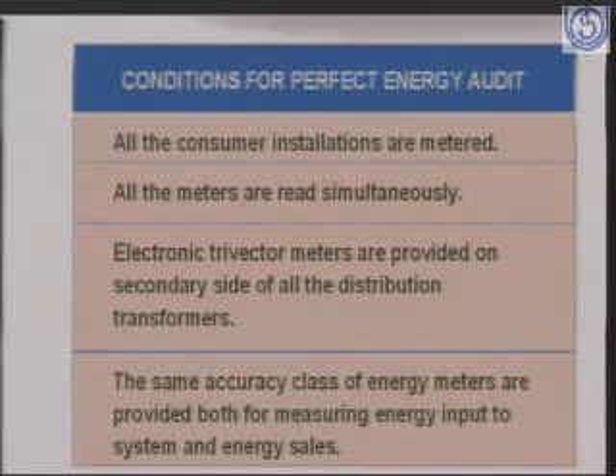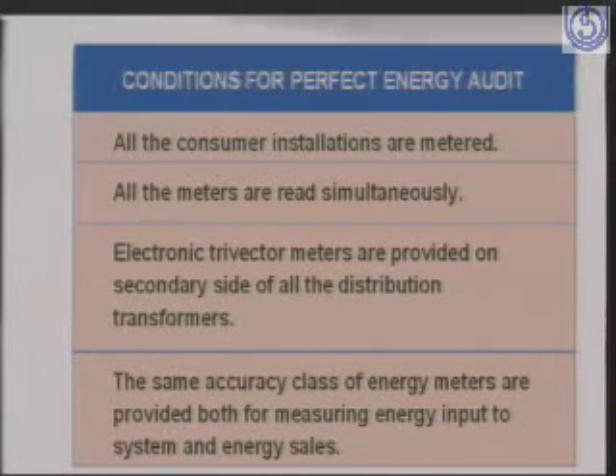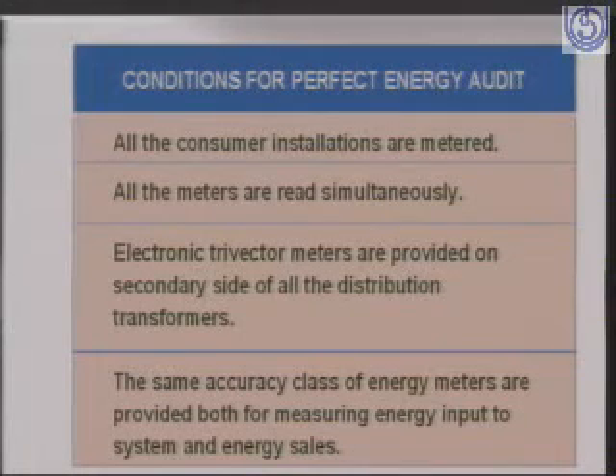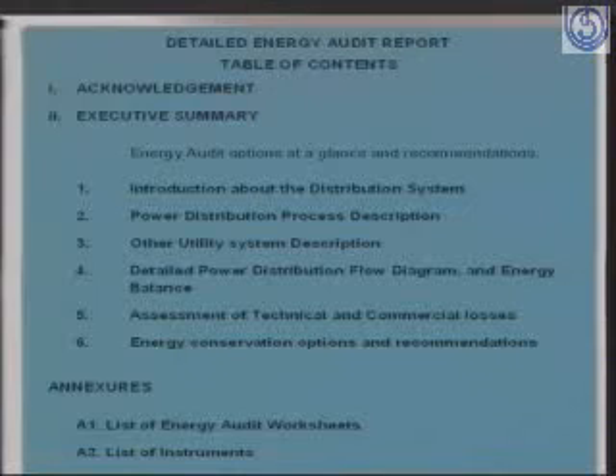So conditions for perfect energy audit: all the consumer installations are metered, all the meters are read simultaneously, electronic trivector meters are provided on secondary side of all the distribution transformers, the same accuracy class of energy meters are provided both for measuring energy input to the system and energy sales. It's very difficult, because you can't provide at the consumer end, at least at the domestic consumer or small consumer, class 0.5 accuracy meters.